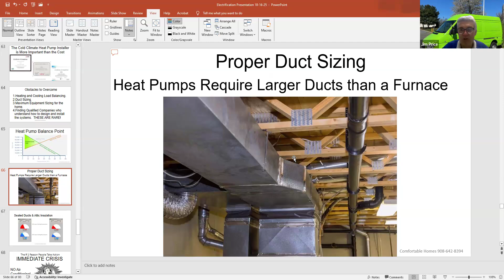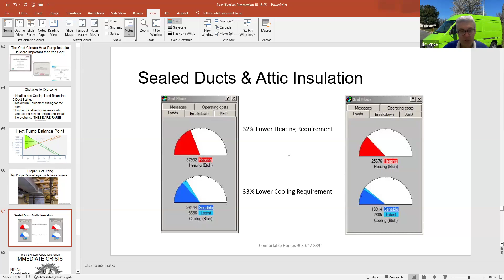Sealed ducts in the attic and insulation, it's critical. We can lower the heating requirement just by sealing and insulating the ducts, by as much as 32%. Where I got these numbers from is a customer where all we did was seal and insulate the ducts, and this was their actual cooling reduction. Their savings was even bigger because they were on propane.